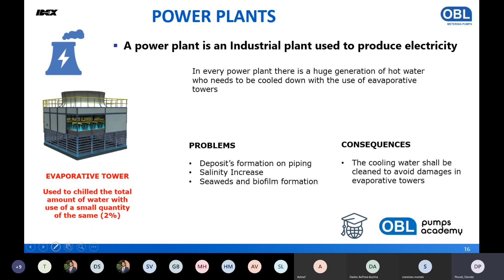So how do you treat water for a cooling tower? Here again is a scheme of the treatment. The water is always very warm and needs to be chilled in this system, keeping a low level of scaling in the water, using antiscalants and corrosion inhibitors. These are chemicals produced by chemical companies with different formulas, but mostly used to keep scale very low and avoid any kind of corrosion inside the cooling tower. The formula depends on the water being treated, so chemical companies always do big studies to understand the best solution.